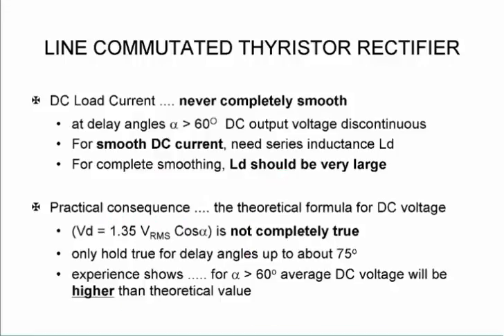Now the DC load current is never completely smooth. At delay angles higher than 60 degrees the DC output voltage becomes discontinuous. So for a smooth DC current what we need is a series inductance, and for complete smoothing that should be fairly large.